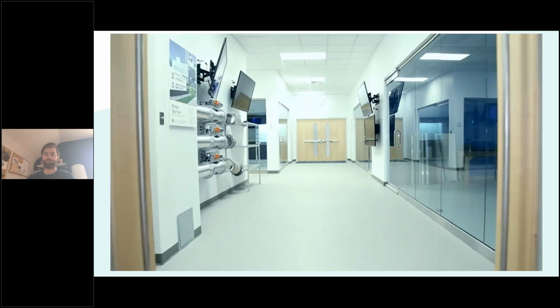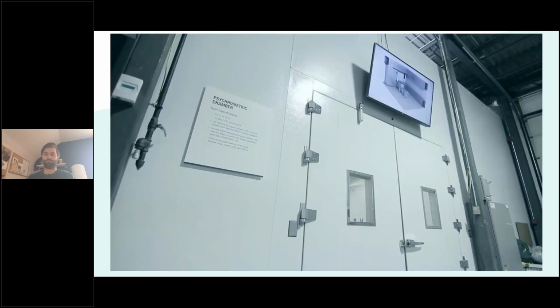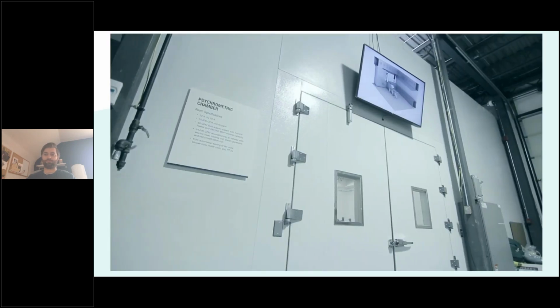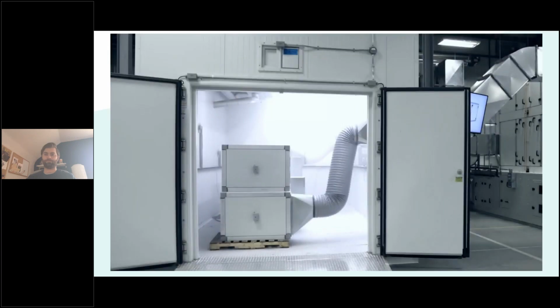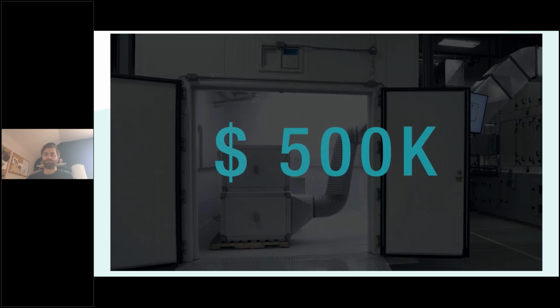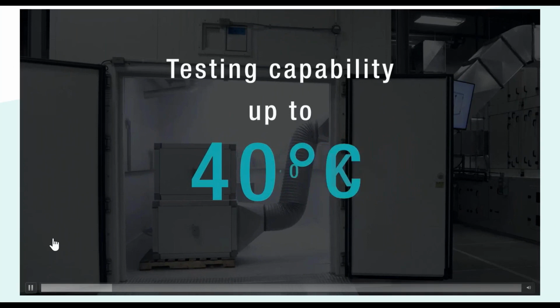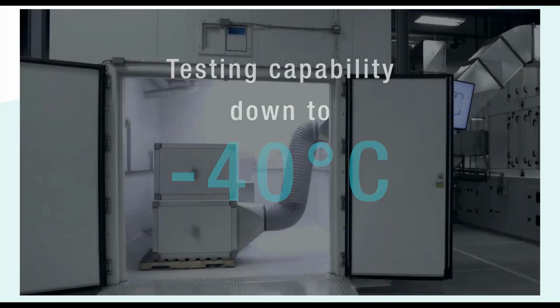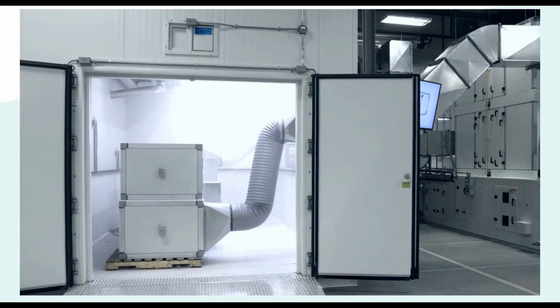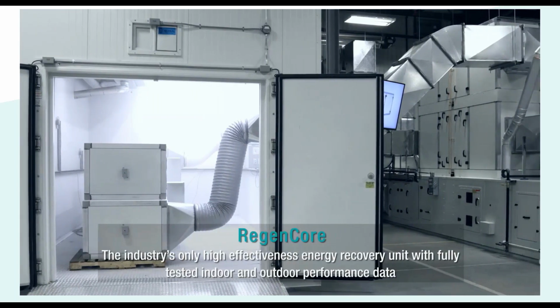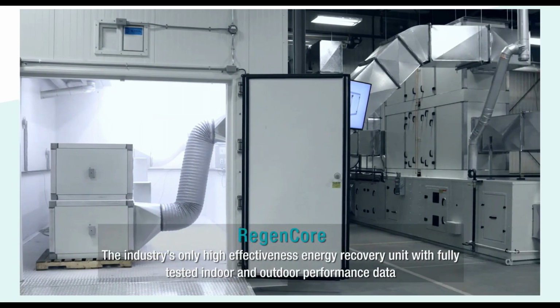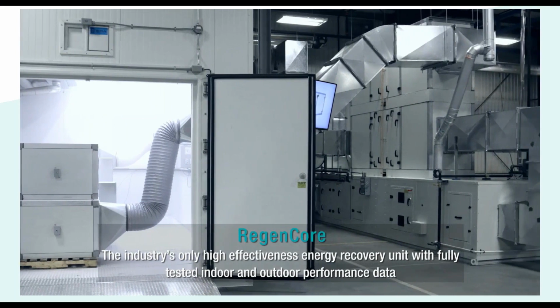SolutionAir's foundation of product development has always been science validated through rigorous testing. This unwavering commitment to R&D has led to the creation of SolutionAir's environmental chamber, a $500,000 investment that allows us to test up to 40 degrees Celsius and down to minus 40 degrees Celsius. This facility has allowed for the development of RegenCore, the industry's only high-effectiveness energy recovery unit with fully tested indoor and outdoor performance data.